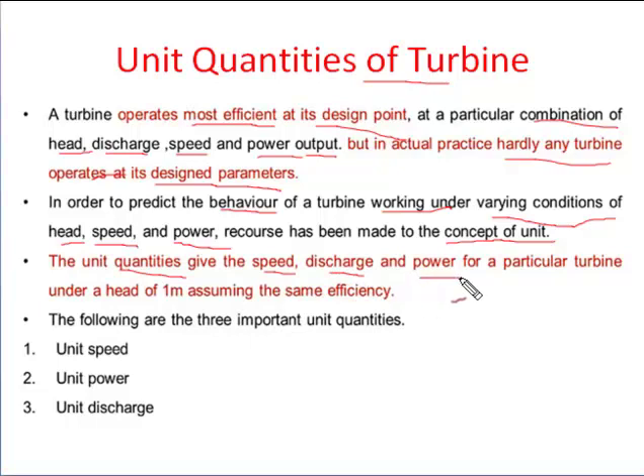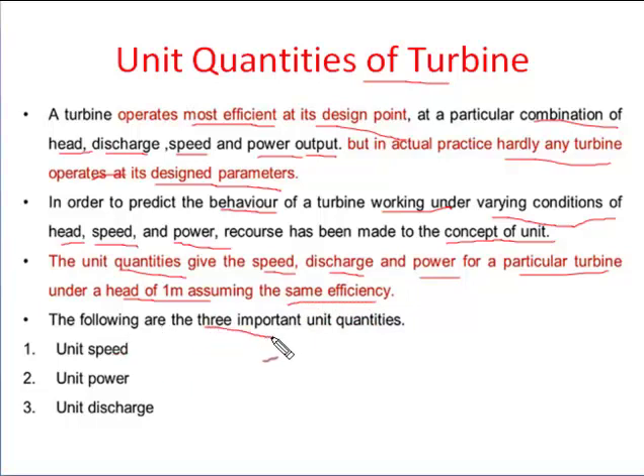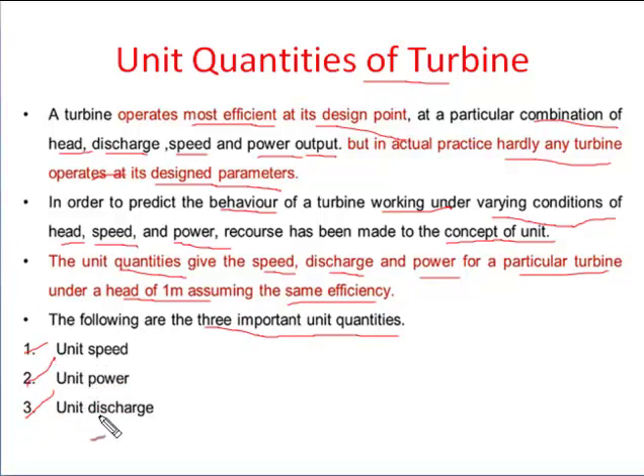The unit quantities give the speed, discharge, and power for a particular turbine under a head of one meter, assuming the same efficiency. The three important unit quantities are: first, unit speed; second, unit power; third, unit discharge.